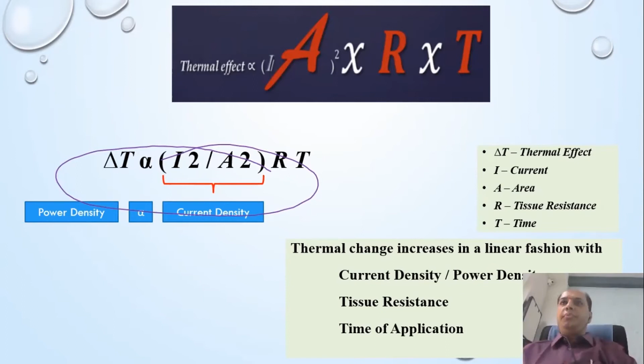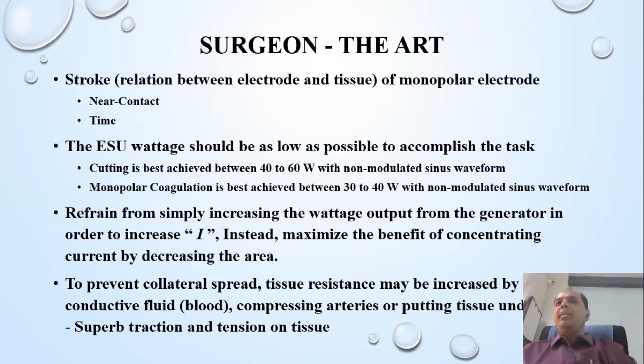The goal of the surgeon is to concentrate the current only at the target tissue and avoid concentration at all other points of the circuit. The speed of the cutting electrode must be optimized to the settings. The surgeon should use the sharpest electrode possible. Watt should be kept as low as possible and he should refrain from simply increasing the power. More concentration should be on making the field dry and stretching the tissue. This is the book from which I have taken the reference material. We must read it if we are using an ESU.